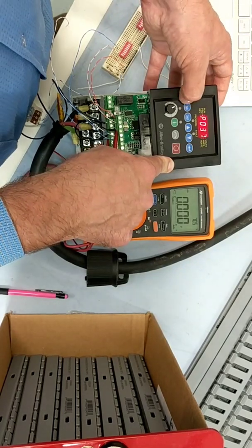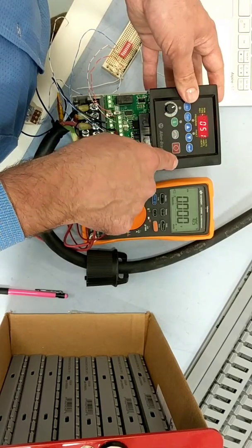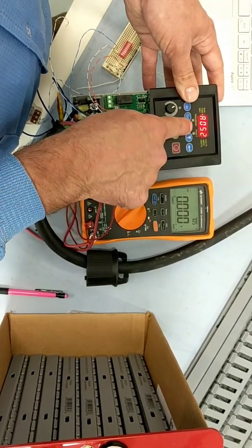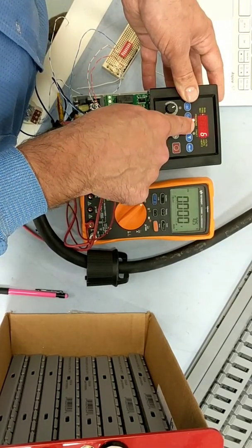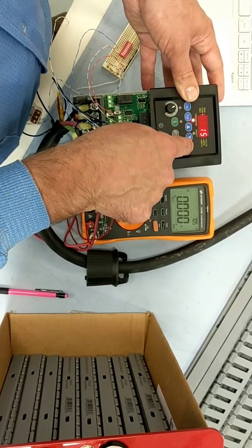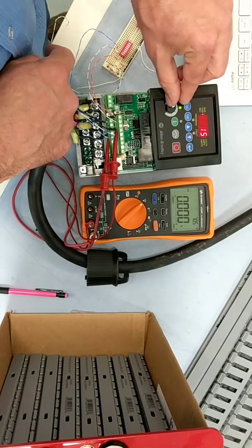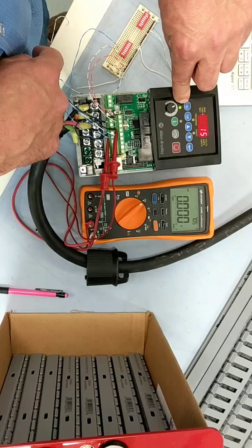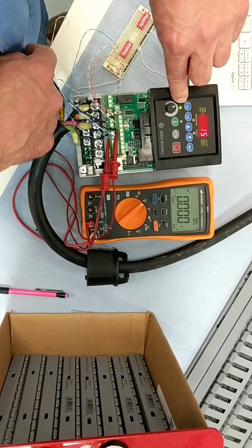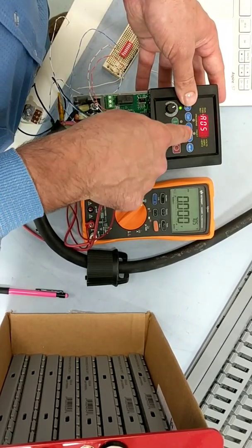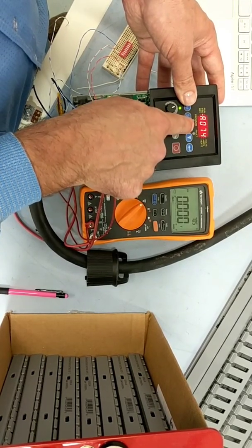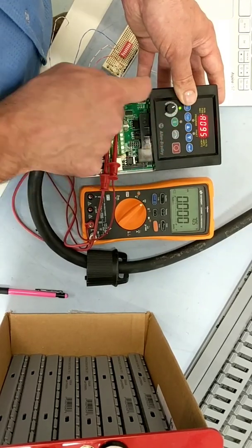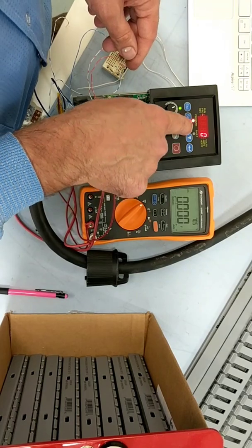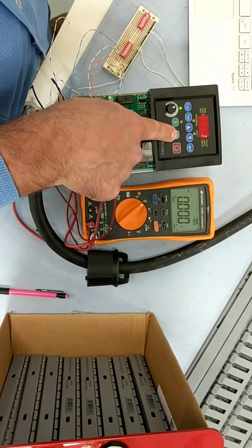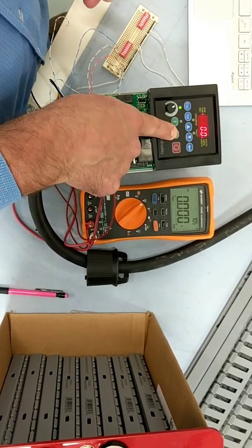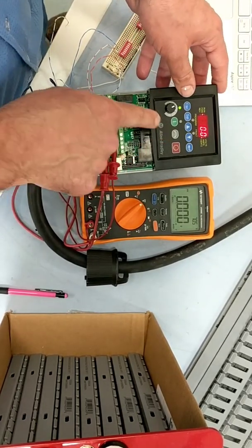Now the A group, so we hit escape to get back to the group. A52 is going to be 15 for PID disable, and when that happened we now see that the LED is on, showing that the front panel potentiometer is controlling the drive speed. A95, this is reverse disable. Enter. And now we can see that the reverse button doesn't do anything. It stays on the forward position.